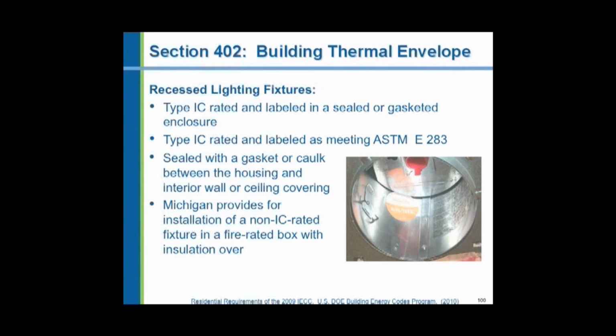The next section talks about insulated ceiling rated fixtures. The National IECC code says that insulated ceiling fixtures must be installed in a manner that prevents infiltration. You have to caulk and seal around them. Michigan has amended that code to allow the use of non-insulated ceiling rated fixtures to be installed. Obviously, if you're putting these in lower floors that are not insulated, you don't have to worry about it. But if you're in the ceiling of the top floor and you're looking at penetrating the roof insulation, the ceiling insulation, then you have to install an insulated ceiling rated fixture. That means you can put insulation right tight up against the sheet metal fixture and not overheat anything. But Michigan says that if you install a box, a fire-rated box with the appropriate clearances over the top of the non-insulated ceiling-rated fixture, they will allow it. But you must seal and caulk that box to prevent infiltration, just as the code talks about for IC-rated fixtures.